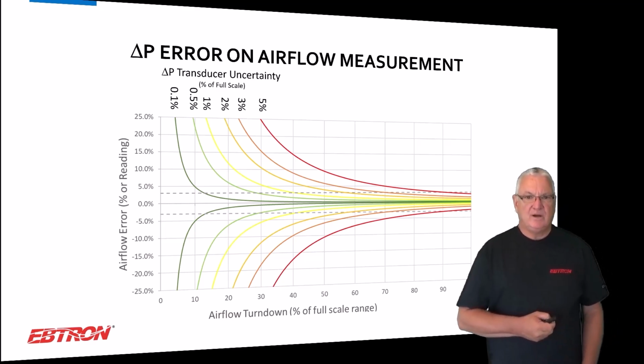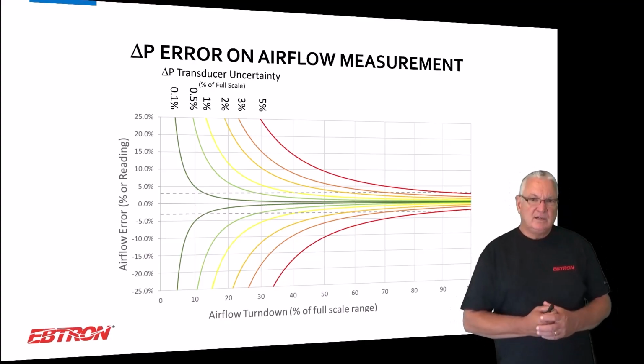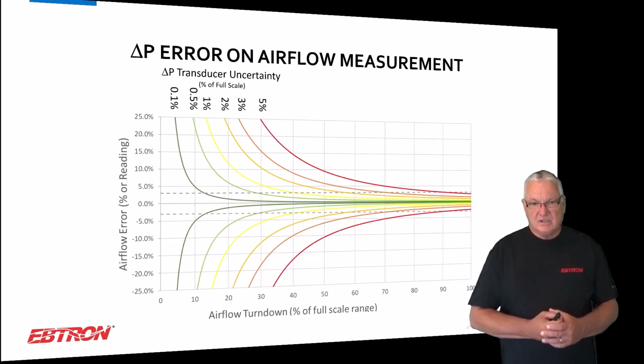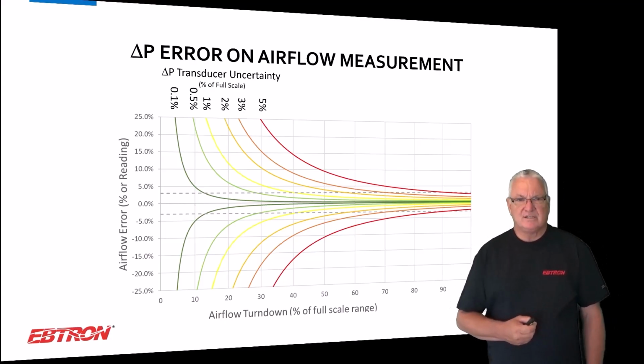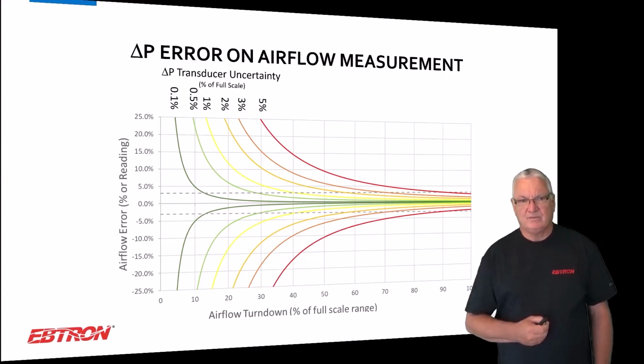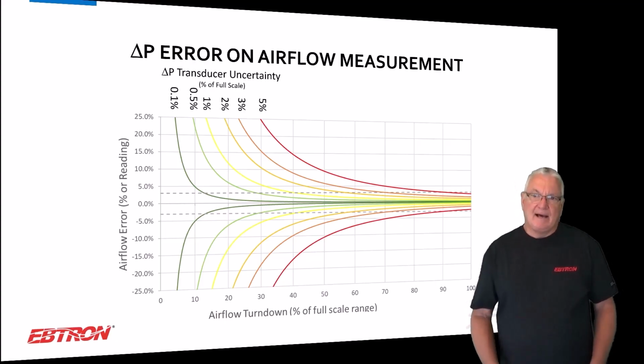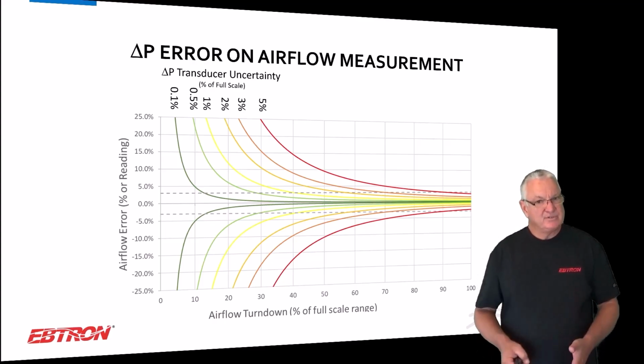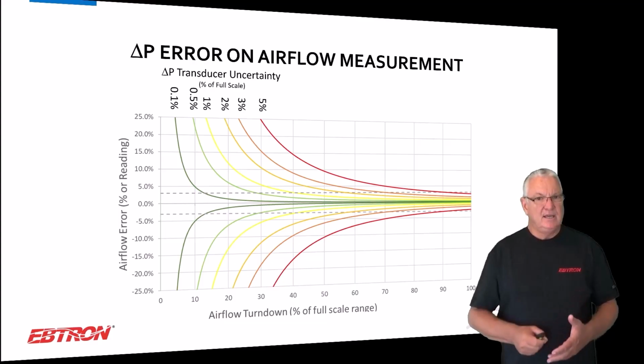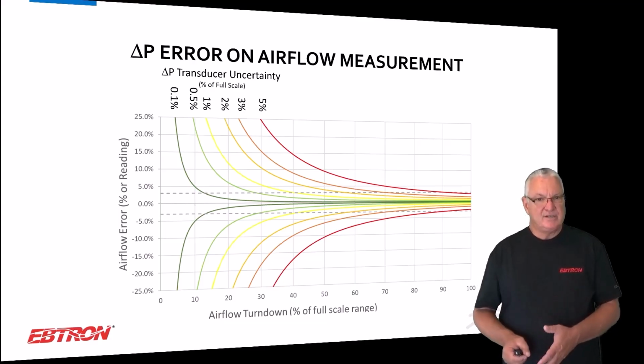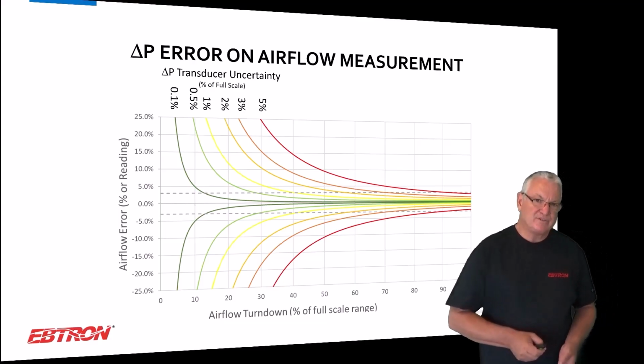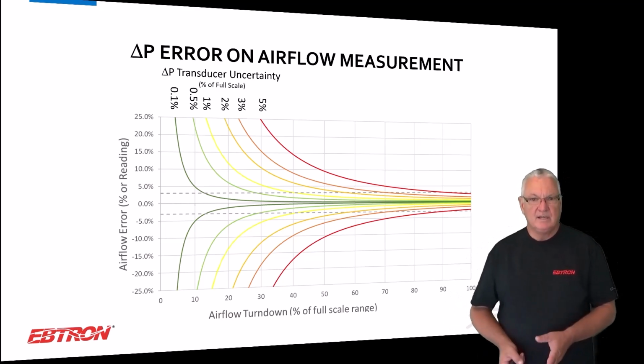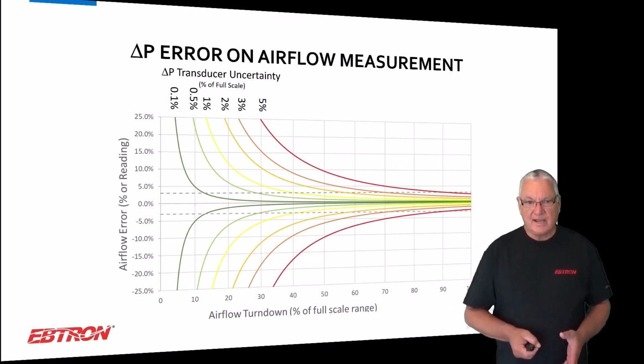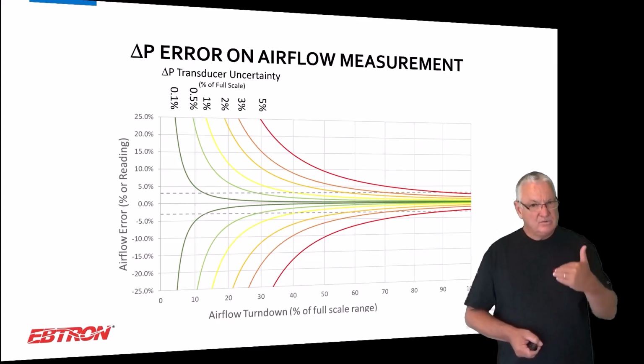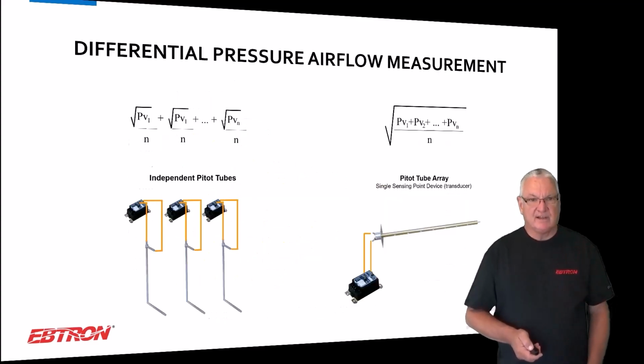Well, all of a sudden you see the uncertainty from the pressure sensor alone is large. And you might say, well, my pressure sensor says it's 0.8% or 0.5%. It's like, yeah, that's out of the box at room temperature. Did you look at the temperature coefficient spec? Did you look at the annual drift expectations of it? And a lot of times a 0.5% pressure transducer will end up closer to 2%. So you want to pay attention to that, okay? Because with turn down, there's some significant error there.